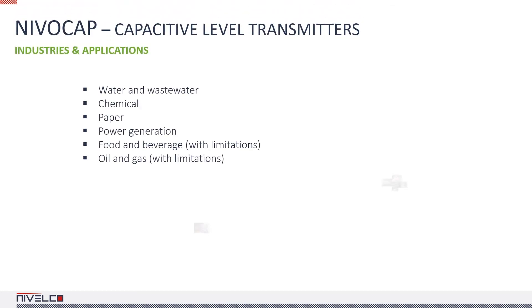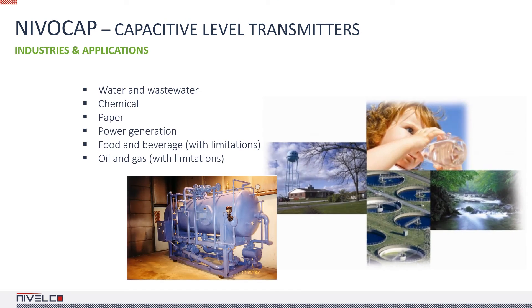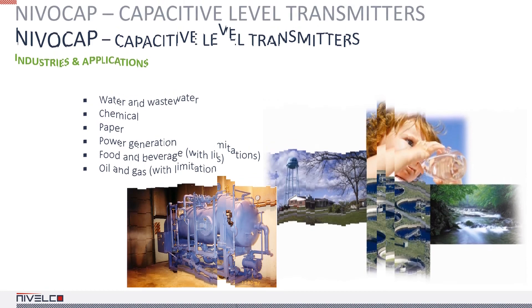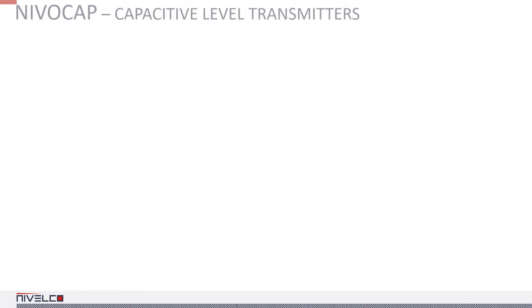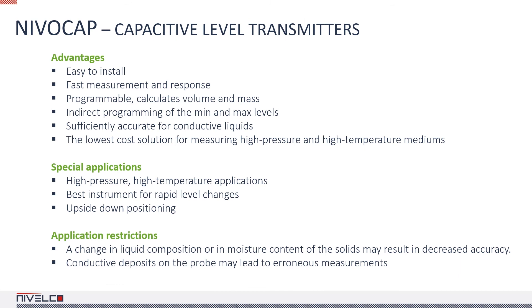The NIVOCAP is a typical level measuring device for the water tank of steam generators. This operating principle requires the medium to be homogenous and that its dielectric constant is at least 1.5. If the tank's walls are non-conductive, a reference probe must be installed. NIVOCAP transmitters are fast, accurate and easy to install. They can be used in applications with rapid level changes and high pressures. However, a change in the composition of liquids or in the moisture content of solids may decrease the accuracy of the system. Conductive deposits on the probe may lead to measurement errors.